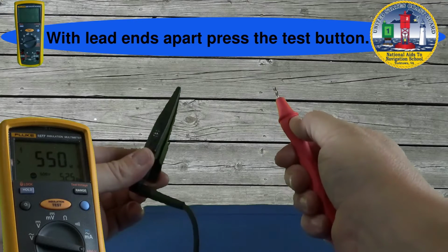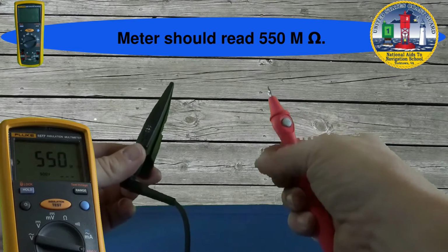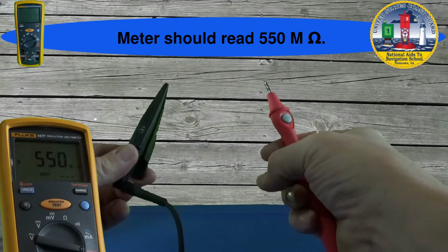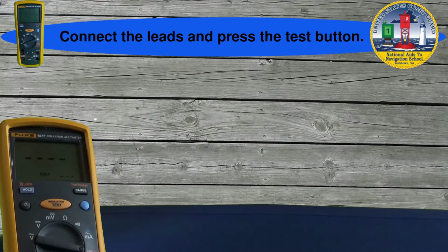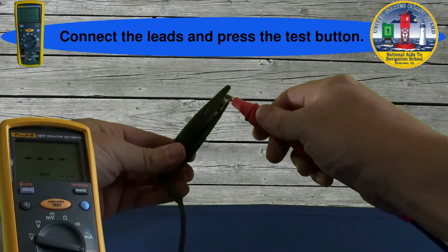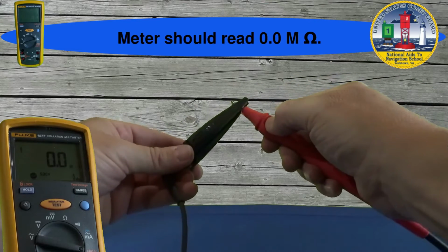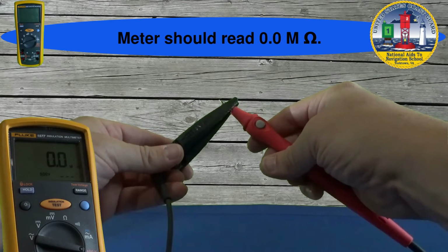With the leads apart and the test button pressed, the meter should read the maximum resistance of 550 megaohms. Short the leads together and press the button. The meter should read no resistance. You have now tested your meter and test leads.